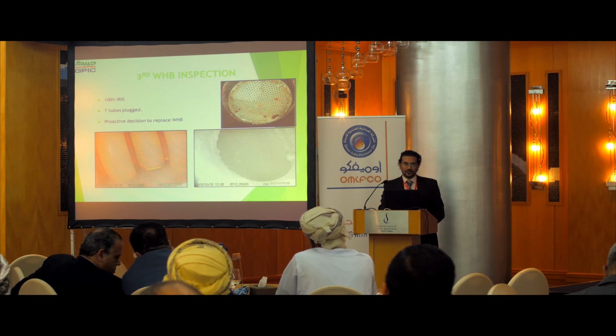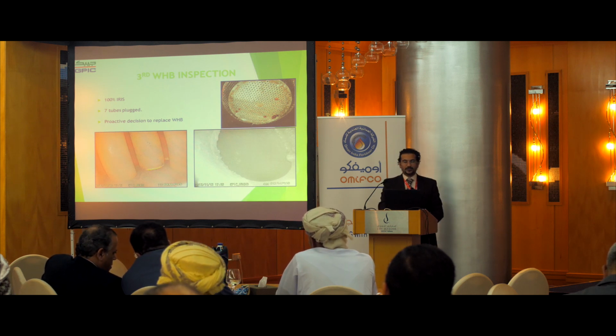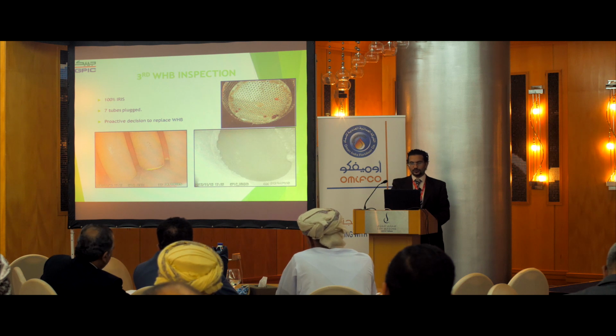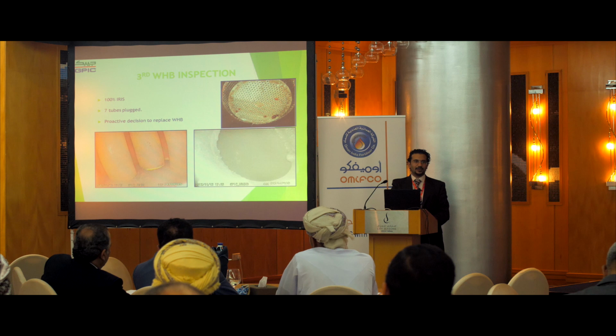And for our third waste heat boiler inspection, we did 100% IRIS on all the tubes. 7 tubes were plugged, not because of leaks, just due to thinning. And as I mentioned before, a proactive decision was made to replace the waste heat boiler.